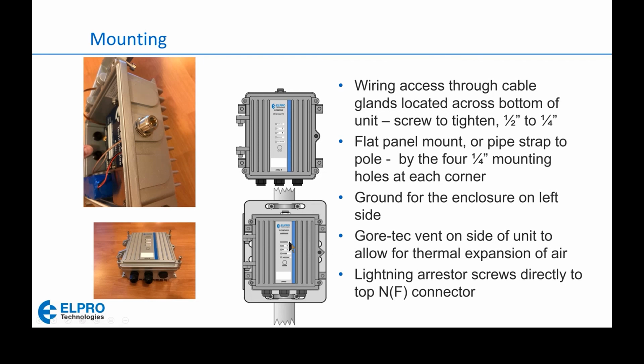So what will happen is an electrical enclosure like this is sitting outside, and it's a cold day. All of a sudden, the clouds clear away, and the sun begins shining on the enclosure. The inside of the enclosure is going to heat up, so you have to allow for that air to vent. So we have this Gore-Tex vent on the side of the unit. It keeps moisture out, lets air in and out, lets the unit breathe, as it will need to. Otherwise, you'd end up with some other issues. It could potentially suck in moisture depending on temperatures inside and out. So we have this vent to prevent that from occurring.